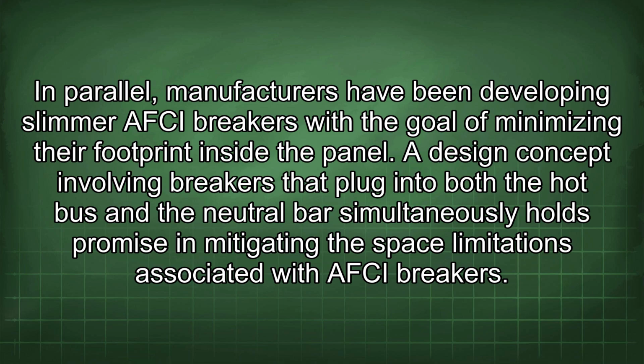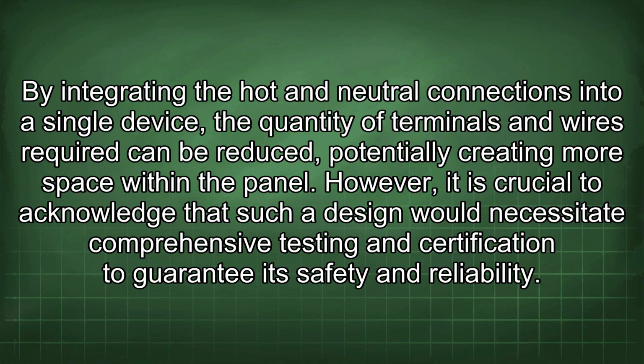A design concept involving breakers that plug into both the hot bus and the neutral bus simultaneously holds promise in mitigating the space limitations associated with AFCI breakers. By integrating the hot and neutral connections into a single device, the quantity of terminals and wires required can be reduced, potentially creating more space within the panel.